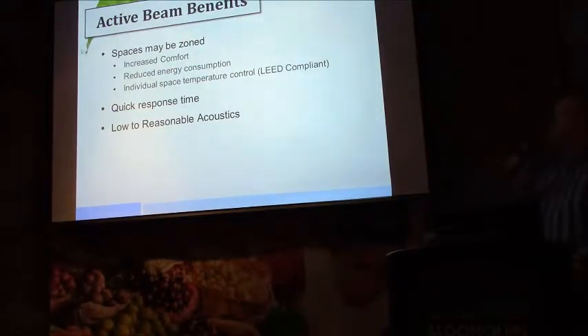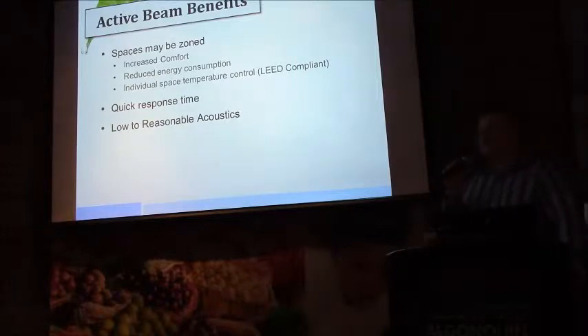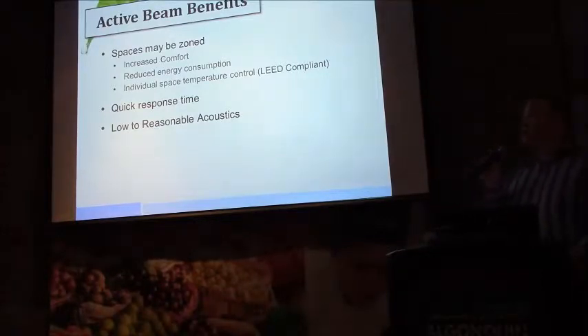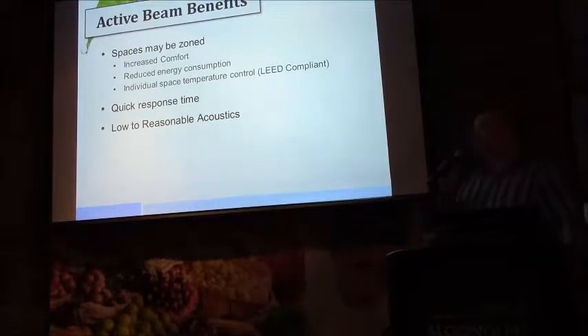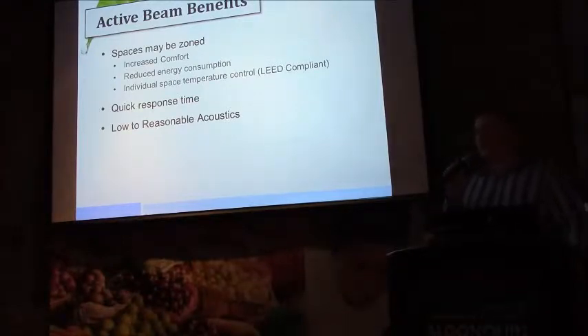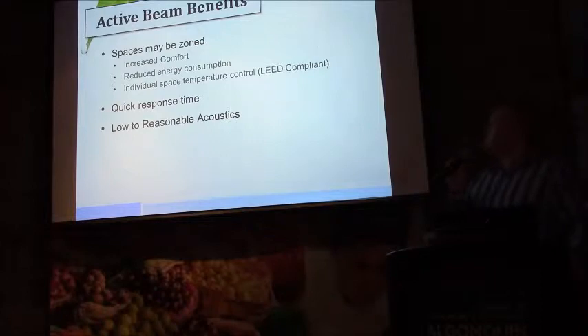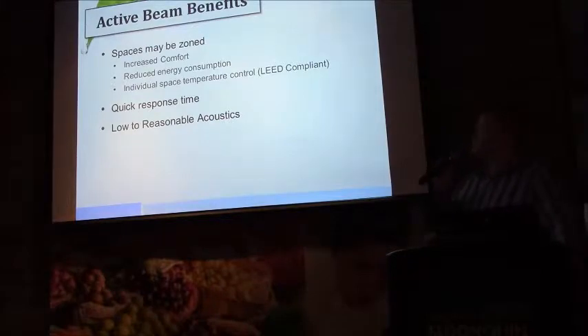And we talked about this, the increased comfort, because of the close approach temperature to the space and the vigorous mixing of the primary air, which is low temp relative to the space as well. And then for LEED compliance, very quick response time. We're swapping out the air in the space at high induction ratios. Let's say we're delivering 100 CFM to a beam, that's 600 CFM of air delivered to the space, turning its volume, and low to reasonable acoustics, again, following the guidelines of lower pressure and smaller nozzles.